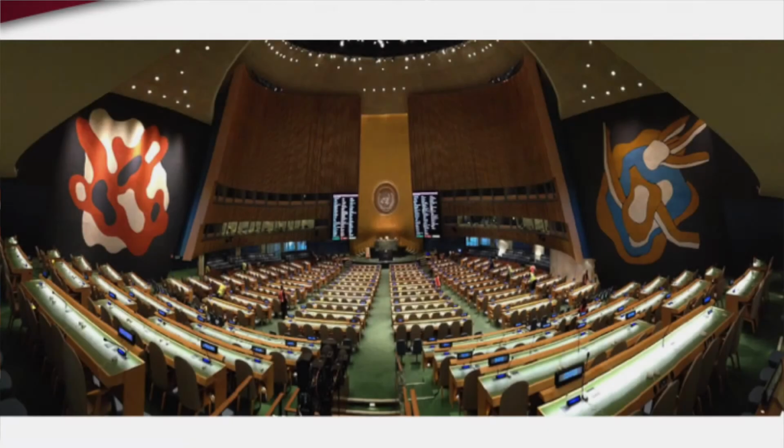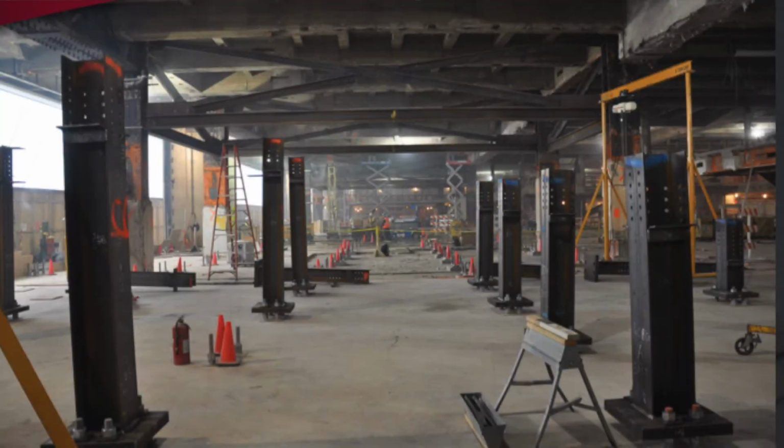That also gave us the ability to install displacement ventilation in these large conference rooms, where we would normally have had, if they stayed the way they were, we wouldn't have had that room to run the ductwork or get the air plenum underneath the conference rooms. So when we were first approached with what to do with this, the engineers at EYP were able to dive in and figure out ways to engineer displacement ventilation into the newly renovated rooms. This is post-renovation. It's kind of more of a fisheye view of it. This is the buffer zone underneath the conference building, one of the mechanical rooms.